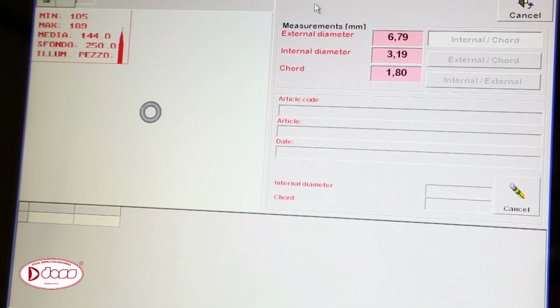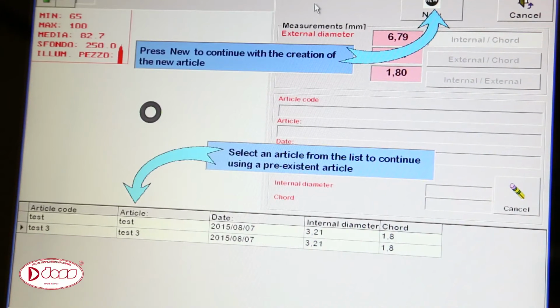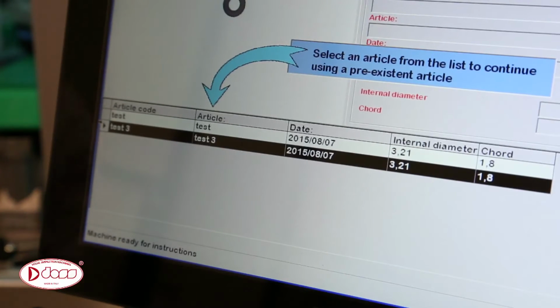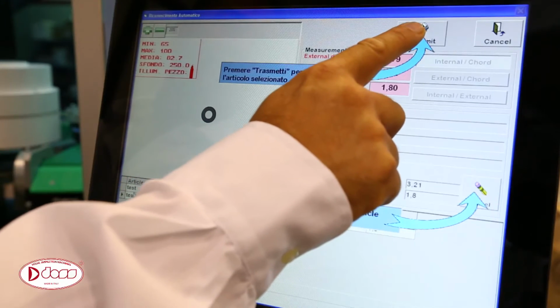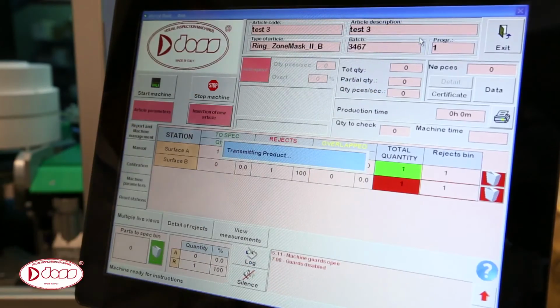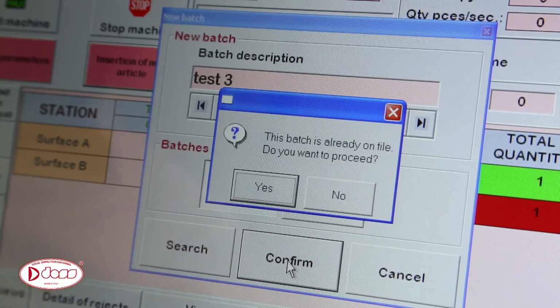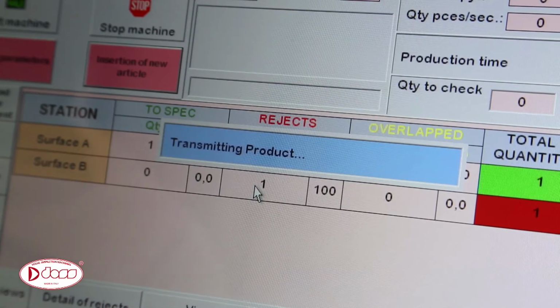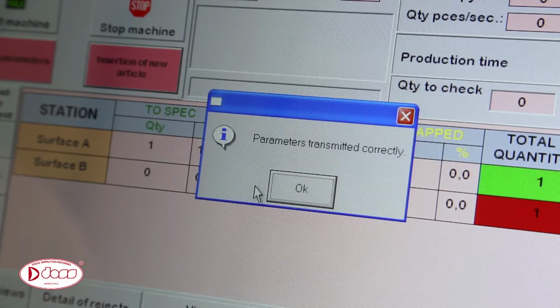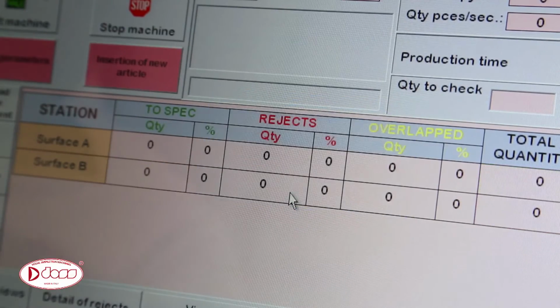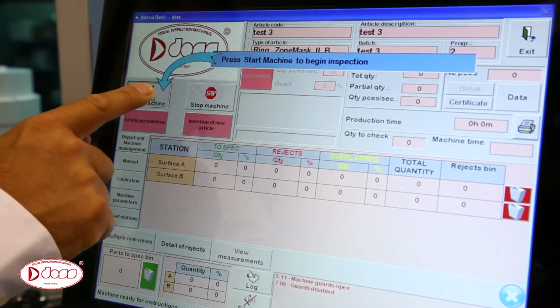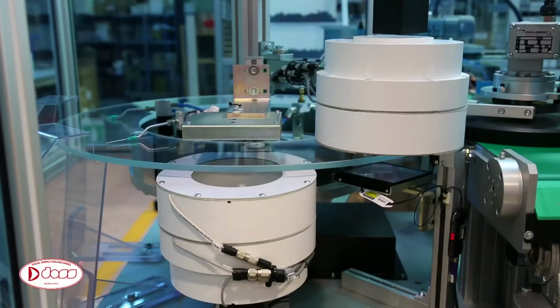After a few seconds, the machine asks you if it's either a completely new one or a part that has already been inspected in the past. So the machine proposes you a list of parts already saved by you under your codification with similar dimension and conditions of light. If it's a part already performed in the past and you want to recall it, you can select from the list the correct item code. If it's a sample already done in the past, you can continue the sorting with the last batch number inserted for this part, or you can start back with a new batch number. Now the machine is transmitting all the information, and in a few seconds the machine tells you that it's ready to start the sorting, and you easily press start.